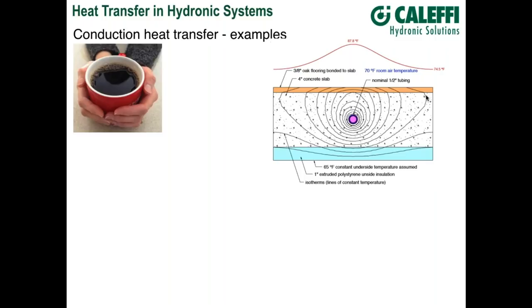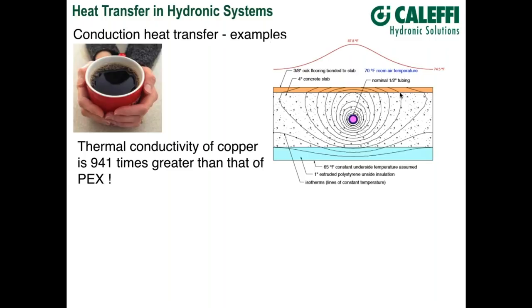Several years ago we did a study comparing different types of tubing embedded in a concrete slab: PEX, PEX-aluminum-PEX, copper, and rubber tube. We looked at the thermal conductivities and tried to assess how much effect a high-conductivity tube would have on overall heat transfer from the slab. The thermal conductivity of copper is almost a thousand times greater than that of a PEX tube. The question is: would using copper produce 941 times more heat output from the floor?